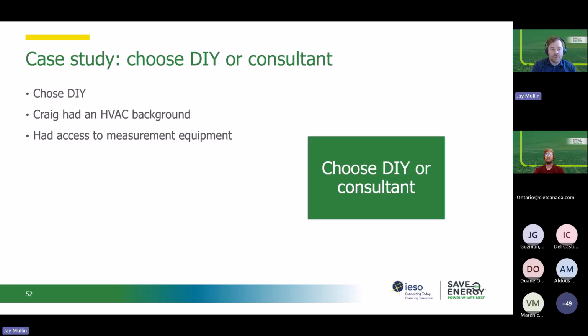And then it came time to choose whether to do it themselves or hire a consultant. And in this case, it wasn't necessarily a simple system. Like I said, they had a lot of points of exhaust, a lot of different points of makeup air. So it was a bit more complex. But Craig, the energy manager there, did have an HVAC background, and as a result of that, did also have access to the measurement equipment. So even though it was maybe a little bit of a more complicated situation, they had that internal capability to undertake the study.